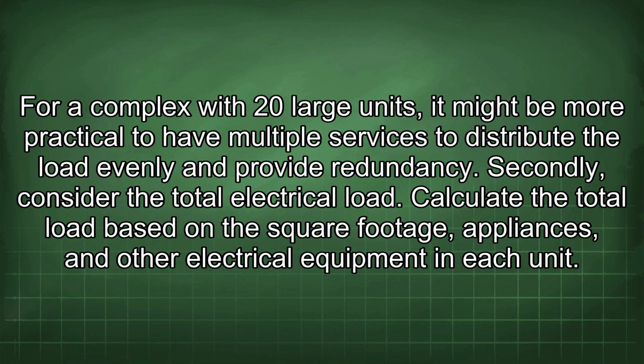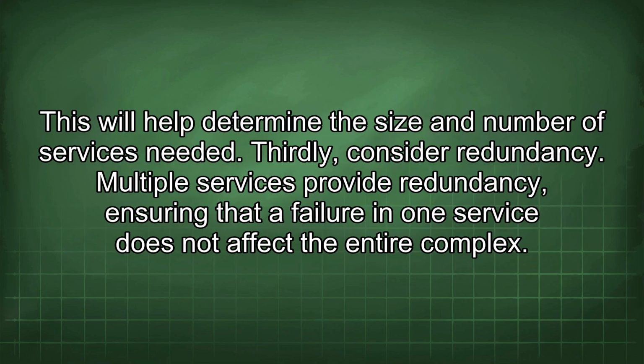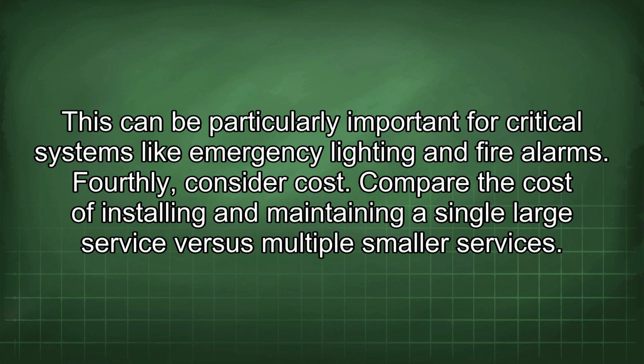Calculate the total load based on the square footage, appliances, and other electrical equipment in each unit. This will help determine the size and number of services needed. Thirdly, consider redundancy. Multiple services provide redundancy, ensuring that a failure in one service does not affect the entire complex. This can be particularly important for critical systems like emergency lighting and fire alarms.